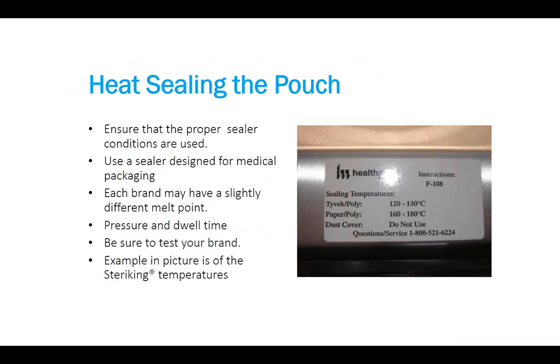As you can see on this heat sealer, it gives you the exact temperature you need. So if you're using this company, you know what it is. When you have different products in your department, you should really standardize with one company because the temperatures could be different, and if you're not in that temperature range, you will not have a good, solid heat seal.